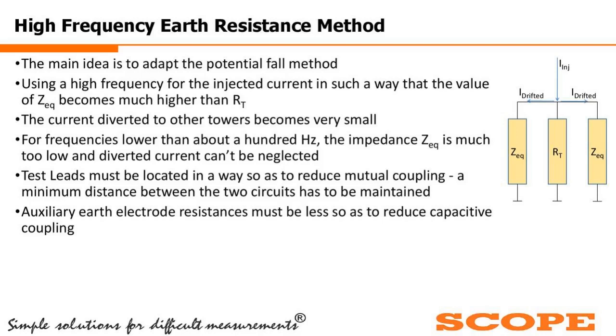Using a high frequency for the injected current in such a way that the value of Z equivalent becomes much higher than RT, as I have explained earlier, the current diverted to other towers becomes very small. For frequencies lower than about 100 Hz, the impedance Z equivalent is much lower and the diverted current can't be neglected. Generally, when the frequency is lower, the Z equivalent value becomes lower, and the drifted current, or the parallel current, becomes higher, which cannot be neglected. So we have to increase the frequency, increase the equivalent value of the Z of the adjacent towers, and then the drifted current can be neglected.